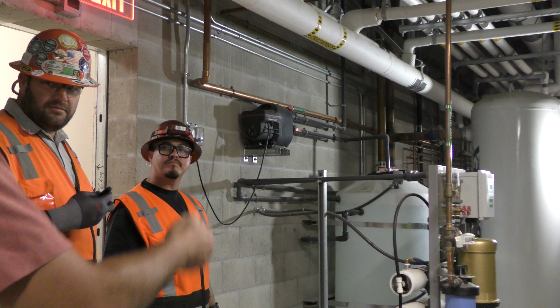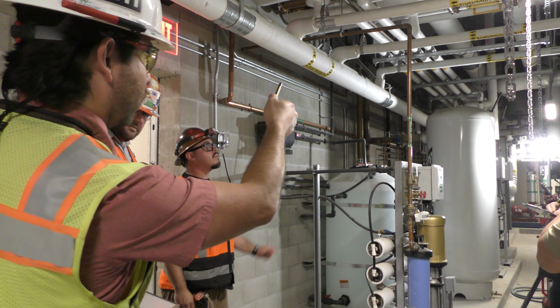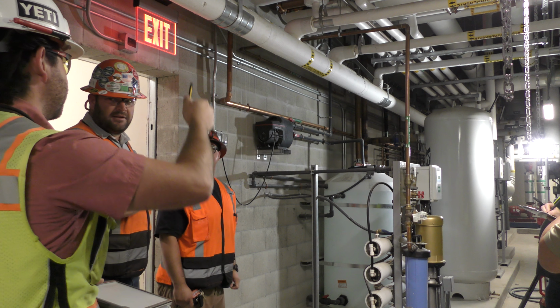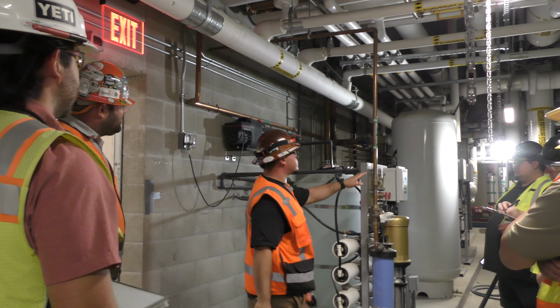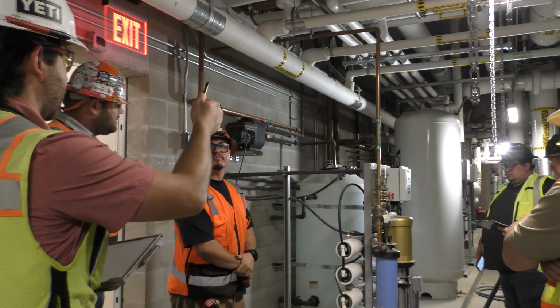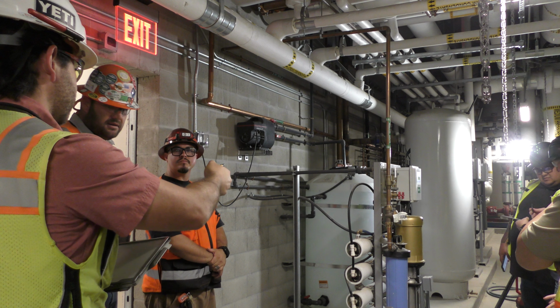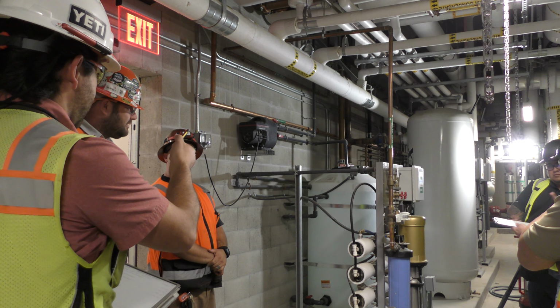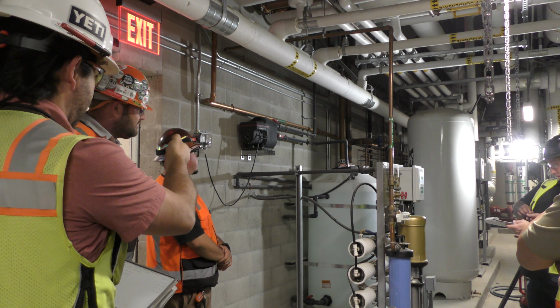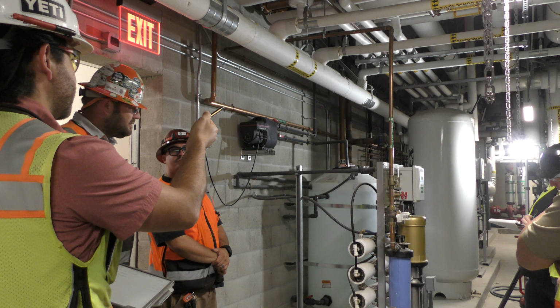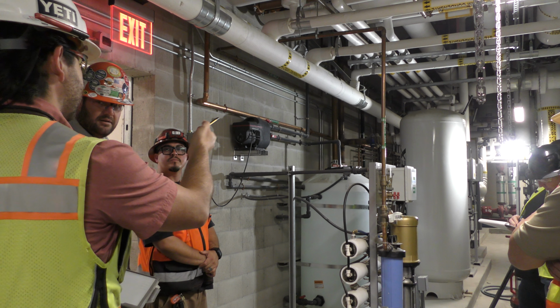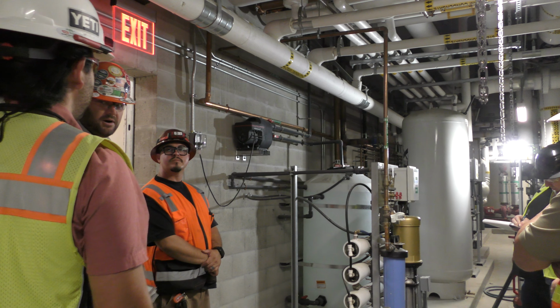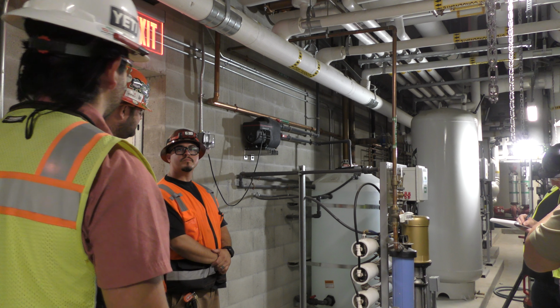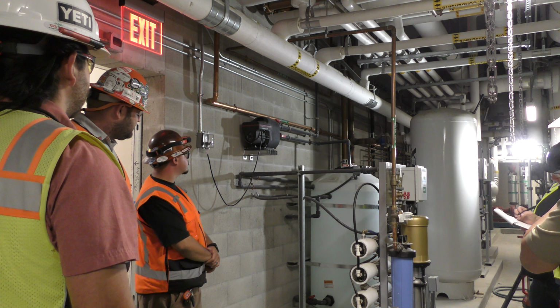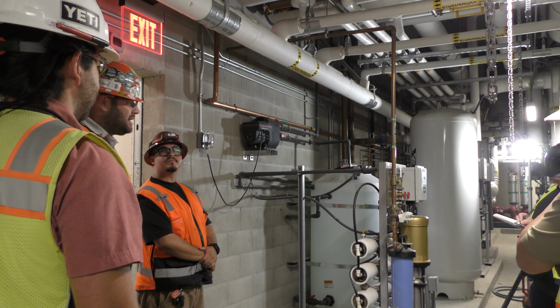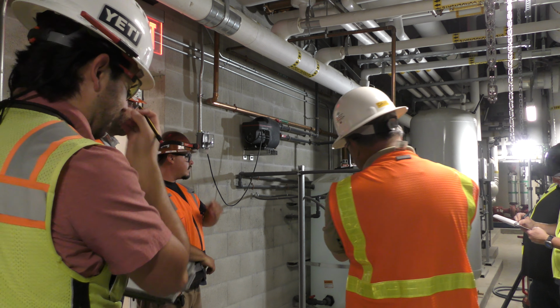All right. So in summary, you got cold water coming in. Domestic water. Soft water. Okay. Cool. So soft water coming in from the tunnel that you got tapped in, goes right into this system with the regulator, and then it goes into the holding tank, which is that bad boy there. So when the boiler, the steam generator, requests clean water, makeup water, that pump itself will trigger, and we'll go from there. Cool. Then we'll let you guys kind of explain the nuts and bolts of your system.